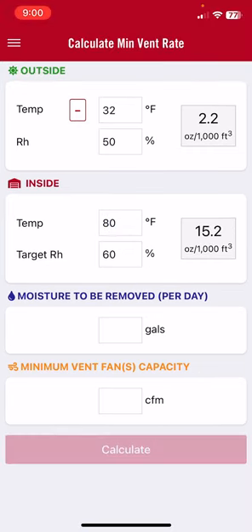Next we put in our inside conditions. Let's say it's about 80 degrees and the humidity is 60 percent. The app calculates that inside the house the absolute humidity is 15.2 ounces of water per 1,000 cubic feet of air. So for every 1,000 cubic feet of air we exchange, we're going to get rid of 13 ounces of water. That's basically how the app works.